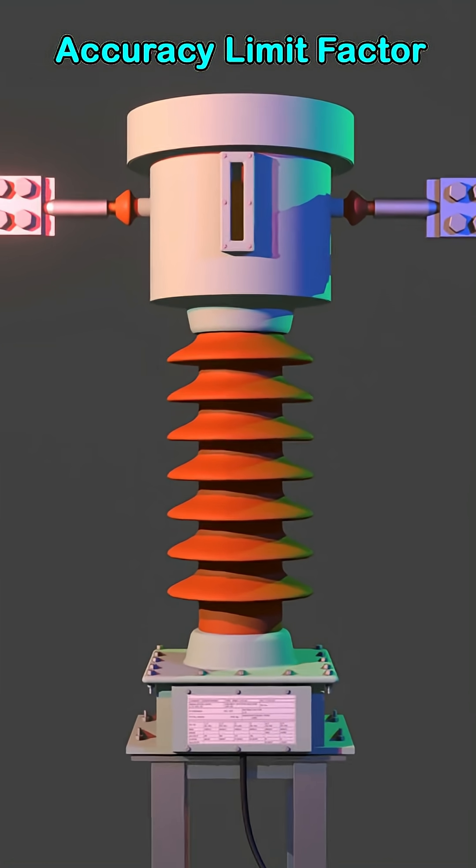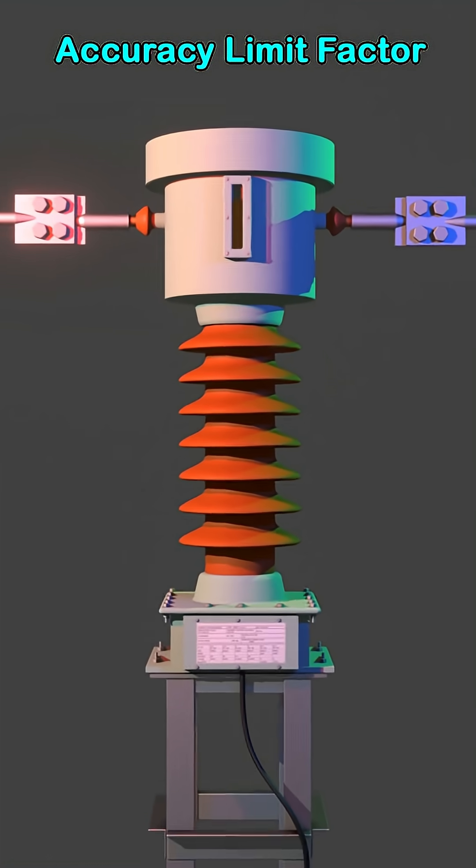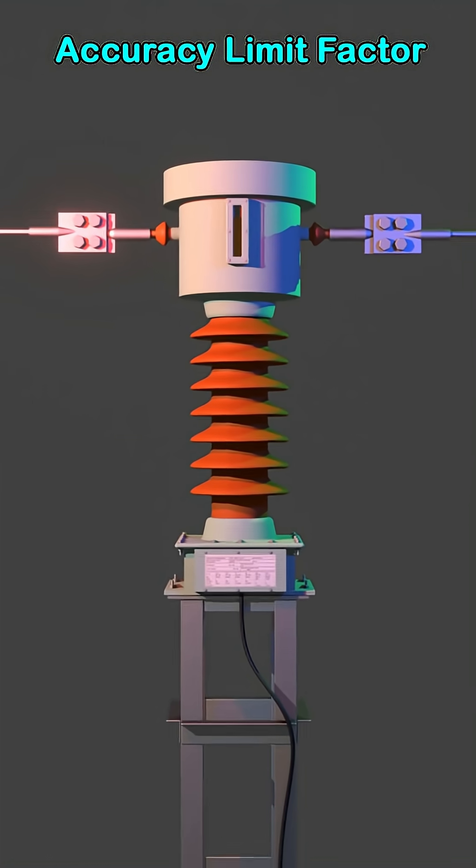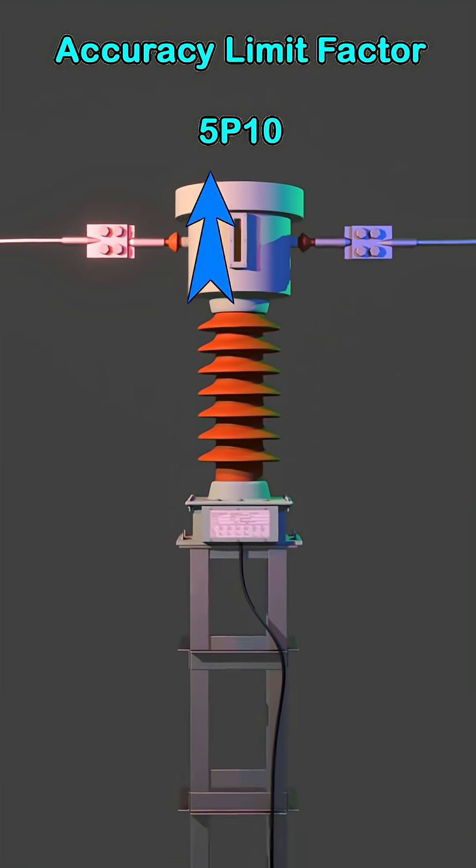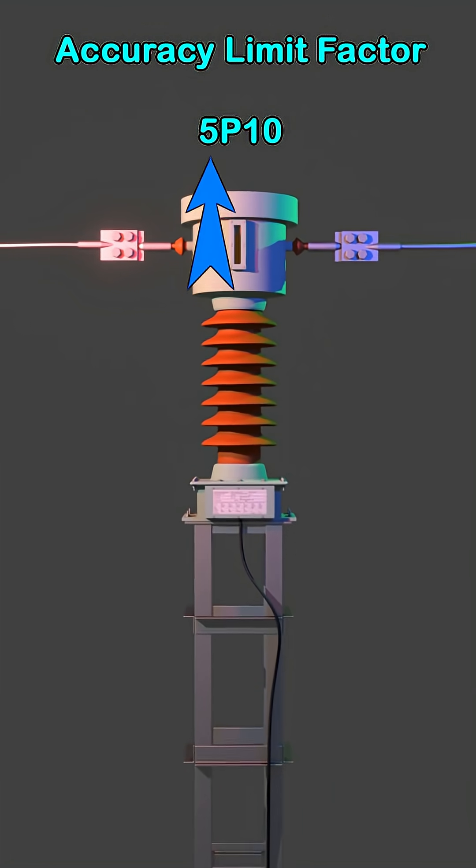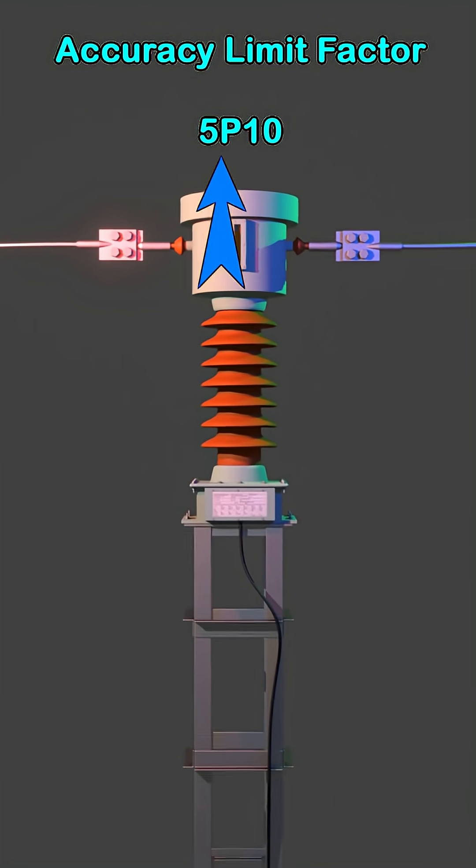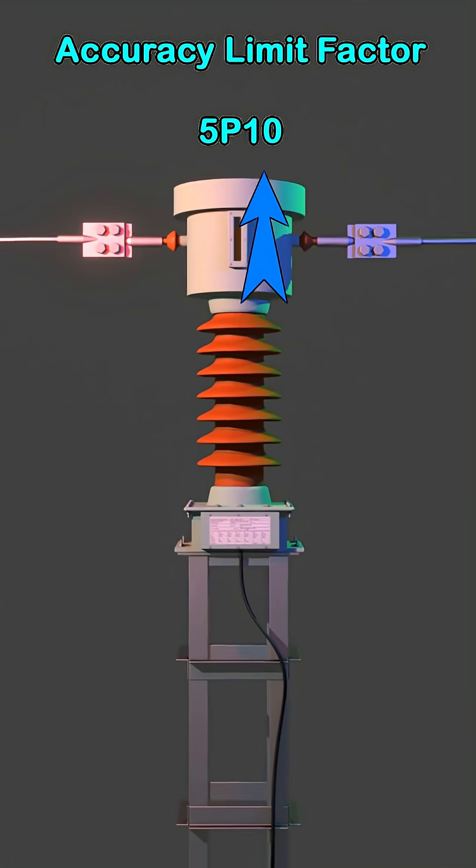To define the accuracy of the protection core of any current transformer, we find notations like 5P10 here. 5 means the percentage of error allowed for the protection core of the CT and 10 is the value of ALF.